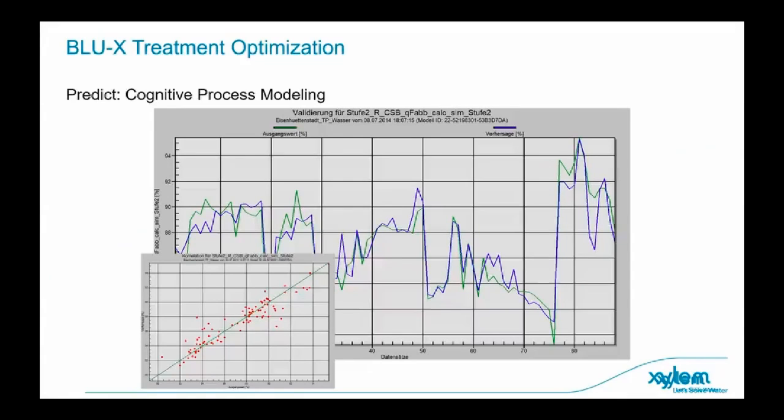So quite frequently when we deploy one of these platforms in the beginning, it will be used in guidance mode. So that means it's just telling the operator how to operate the plant. These experienced operators, which are becoming rarer and rarer, will be able to say, well, that looks like a perfectly sensible way of operating the plant. And then they will follow the guidance. And once they're comfortable with the guidance that's being given, they can then switch it over to automatic mode, and it will automatically make those adjustments to the operation of the plant.